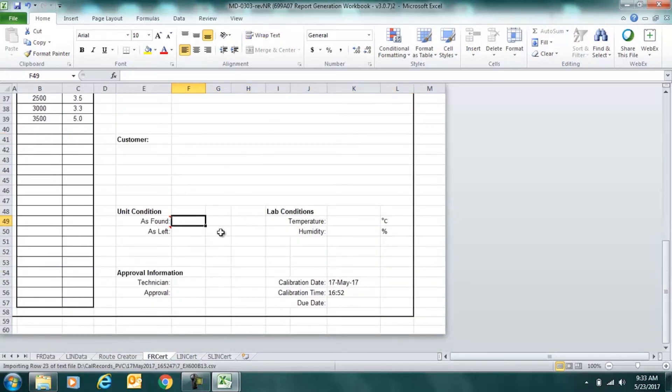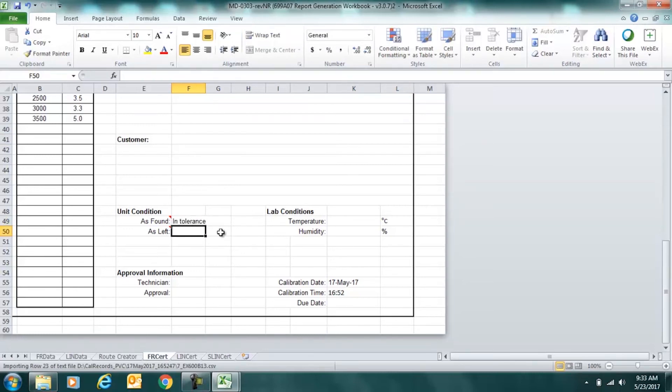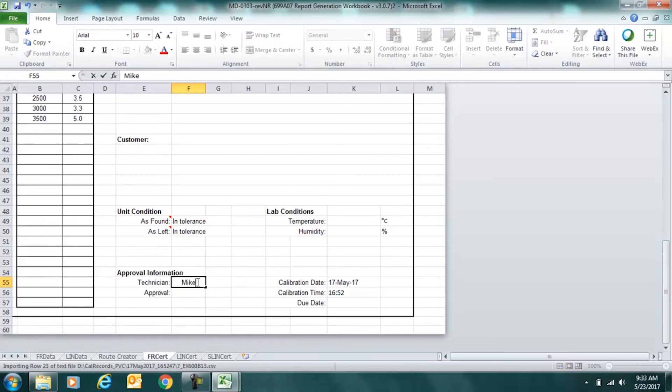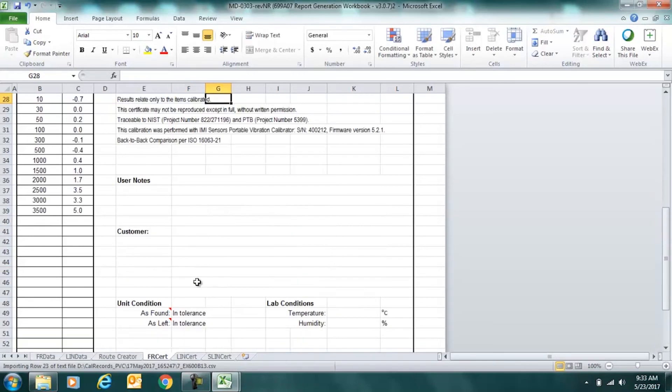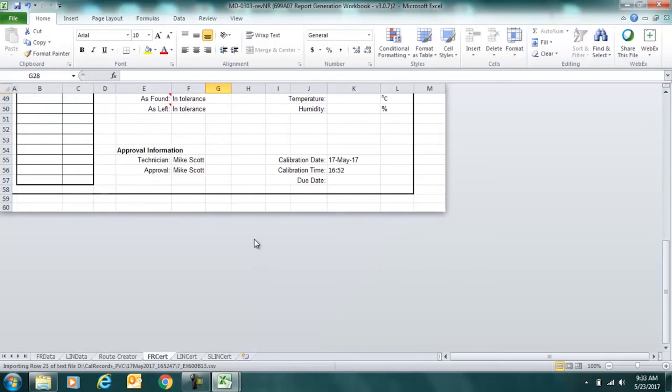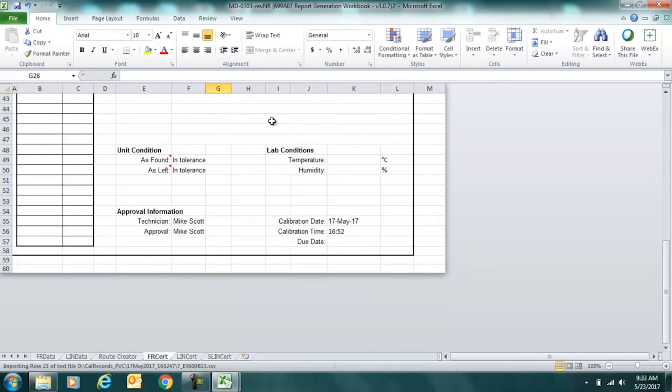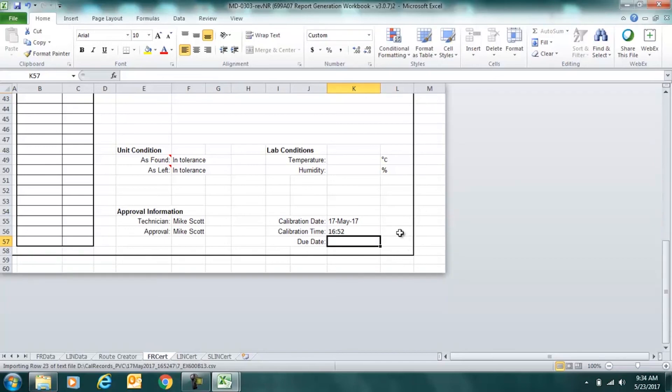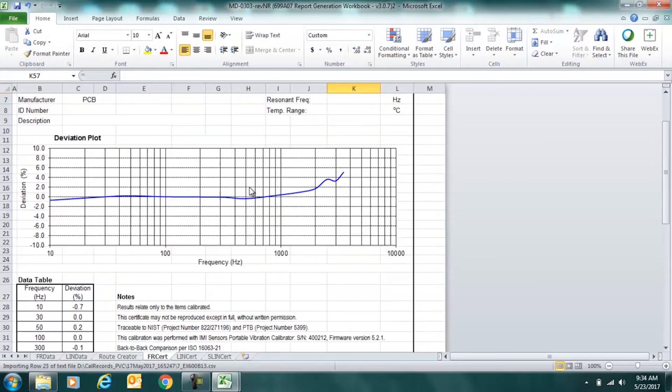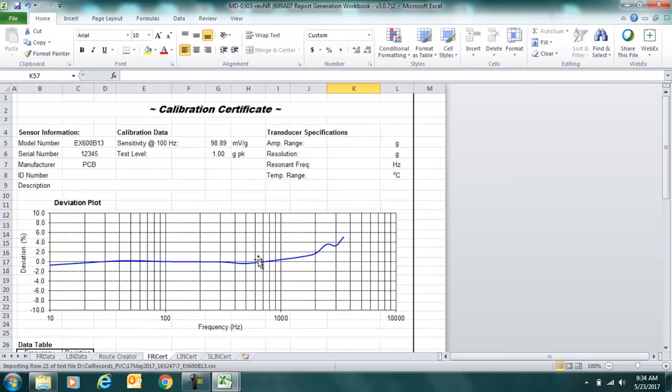As found, this unit was in tolerance and as left, it's also in tolerance. We can enter the name of the technician here and I'll self-approve my calibration. The calibration date and time appear here, which is also critical to ISO 17025 compliance. And we can enter a due date if we'd like here or leave it blank. And that's the calibration certificate.